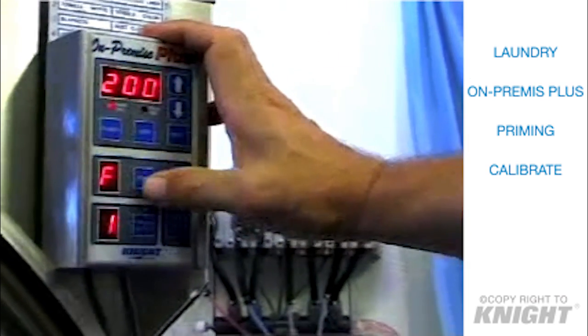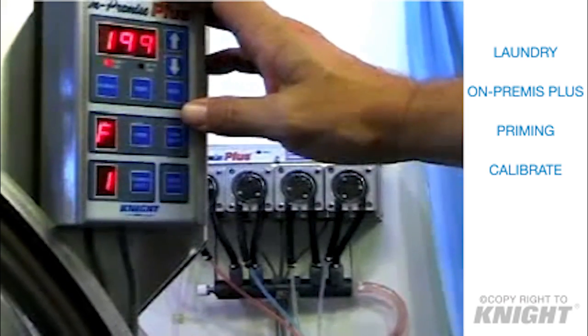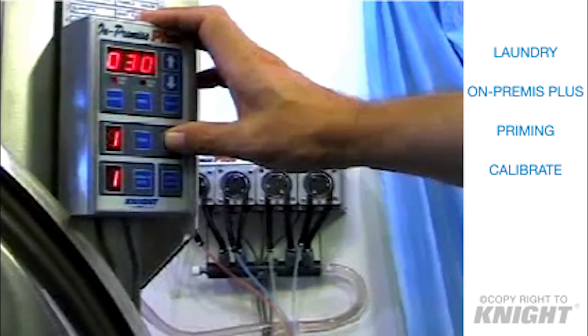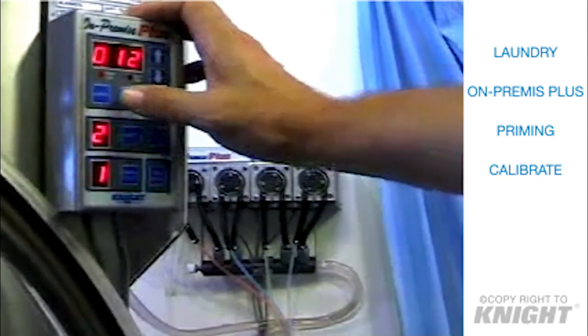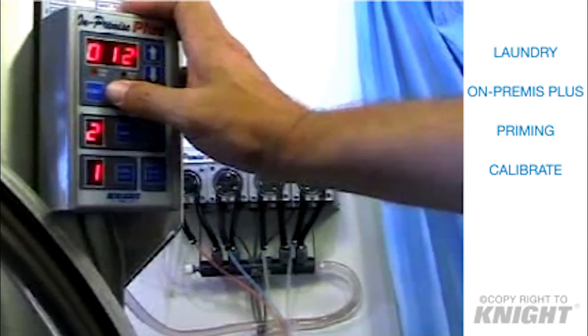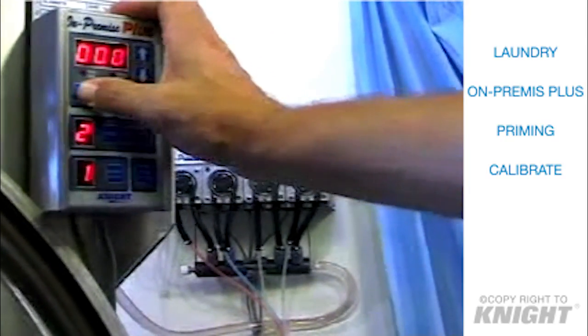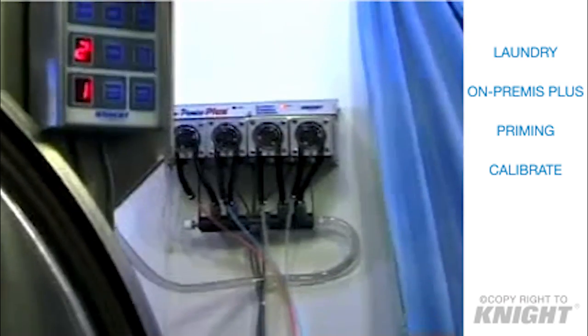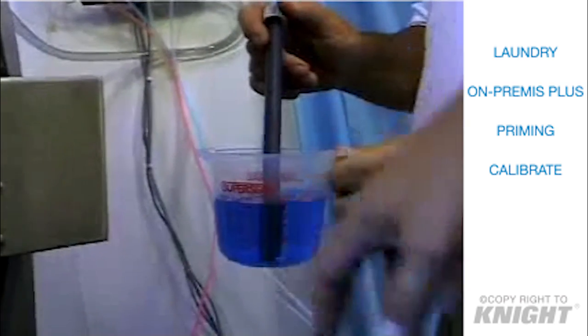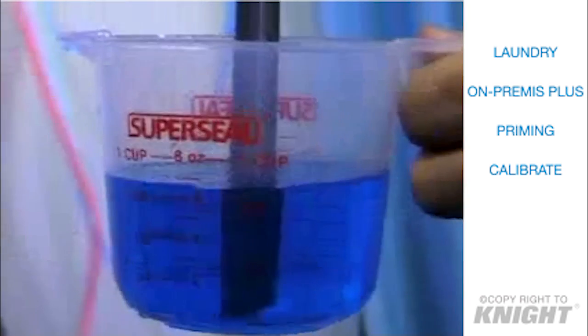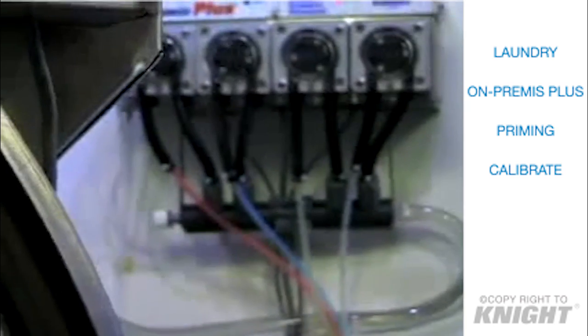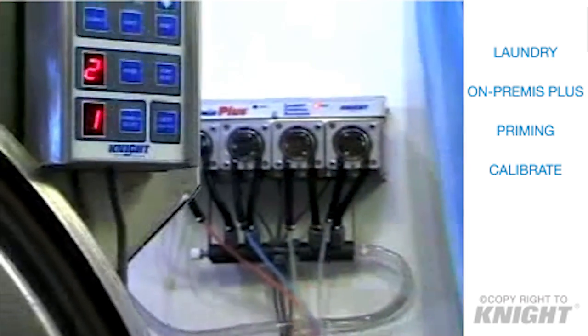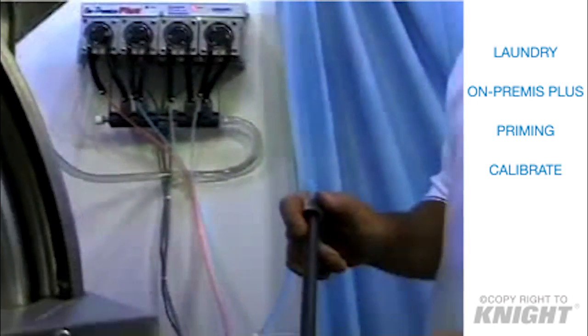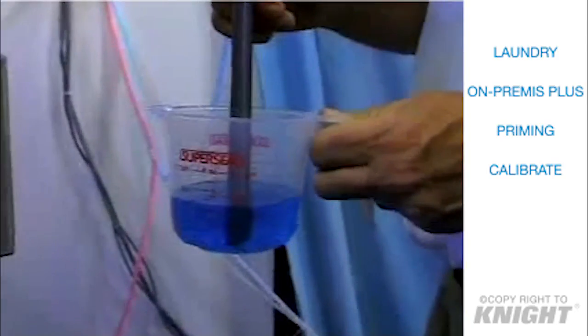Select your flush pump, press prime. Now select the pump you want to calibrate, pump 2 in this case, and press the calibrate button provided the pump time LED is flashing. Now pump number 2 will begin to draw off of our supply. Now we're going to run that for at least 30 seconds. You can run it longer if you like, but we're going to draw off a little bit more material here than we did the last time. The longer you run the pump, the more accurate your calibration is going to be.